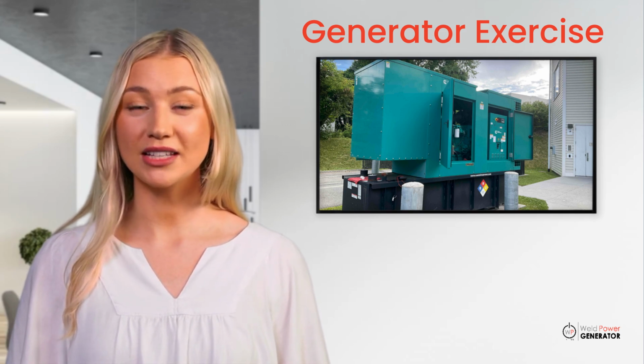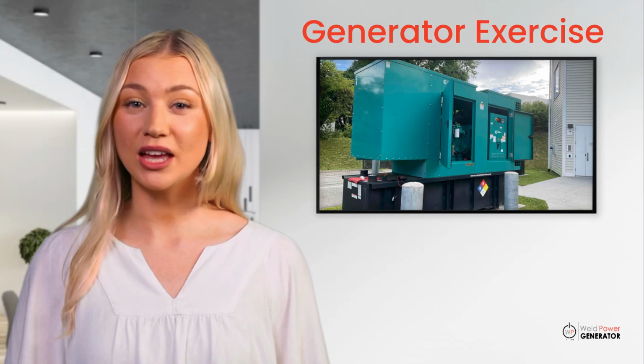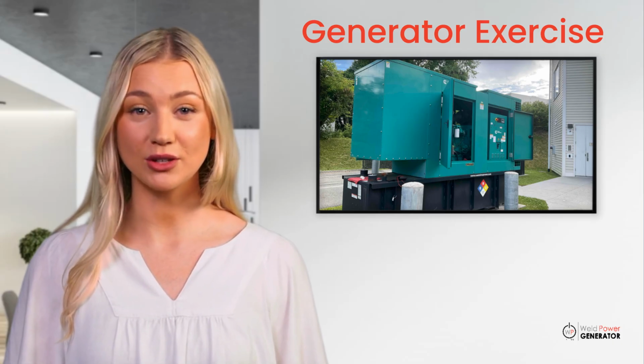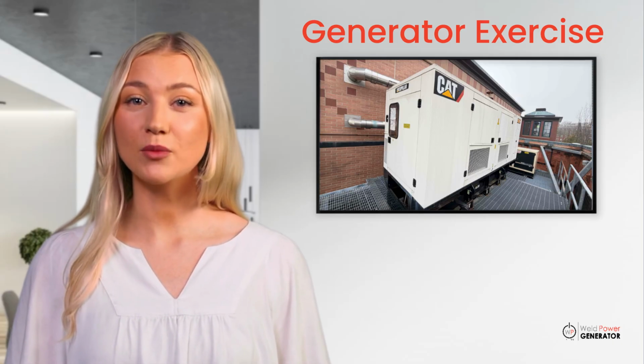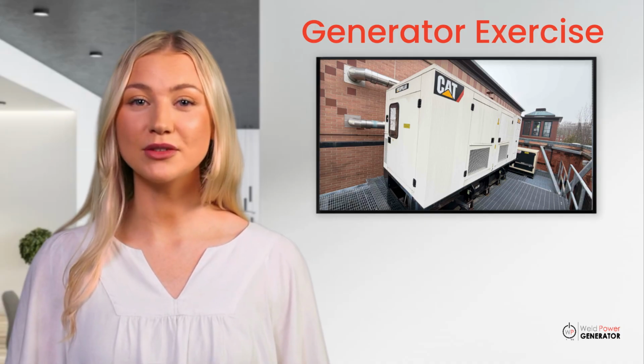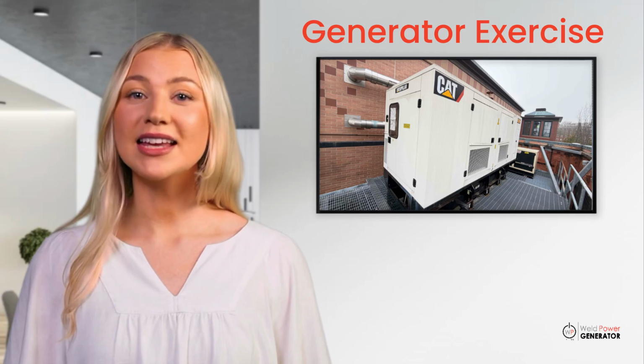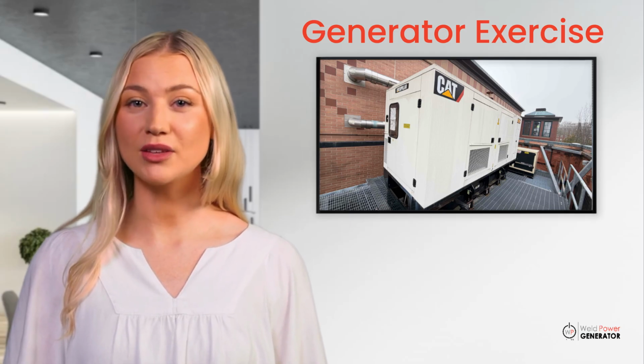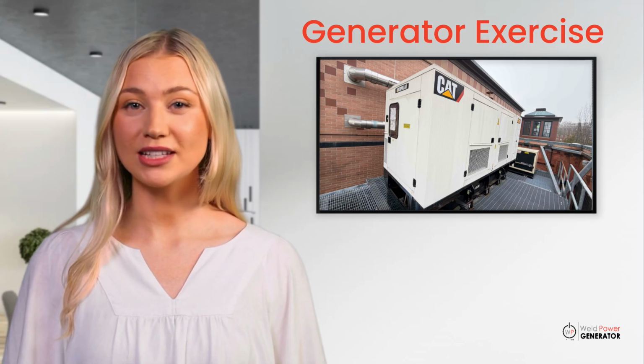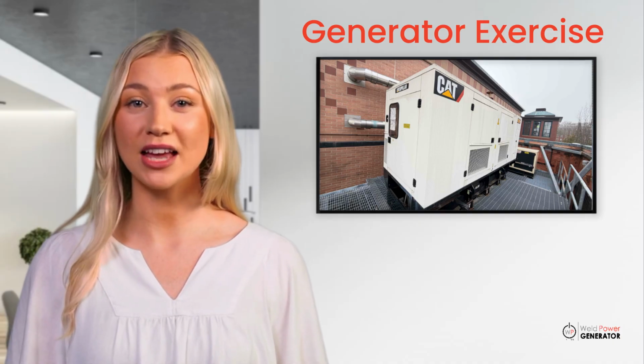Unloaded, no-load runs may seem sufficient, but they don't generate enough heat to burn off moisture and combustion byproducts from cylinder walls and exhaust systems. Over time, this leads to wet stacking in diesel generators, a buildup of unburned fuel and carbon deposits that degrades performance and accelerates engine wear.